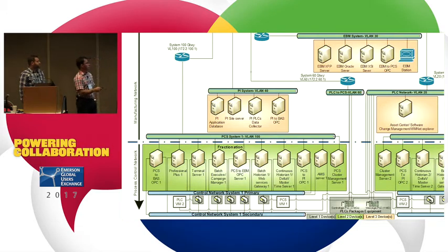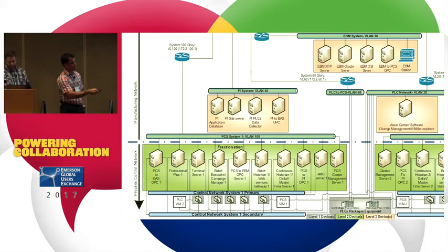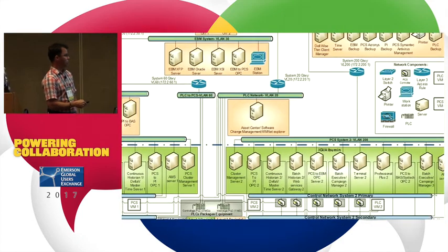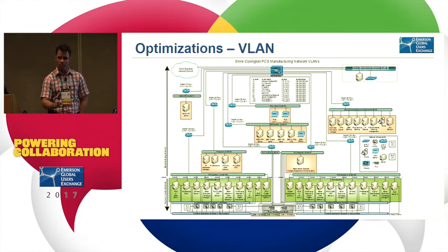Then each plant LAN connection has an IP address on this VLAN: the one for the fractionation system, and the one for the other system, the IG albumin system. So it is important to say that we are not using VLAN for process control. We keep the typical Emerson recommended design.